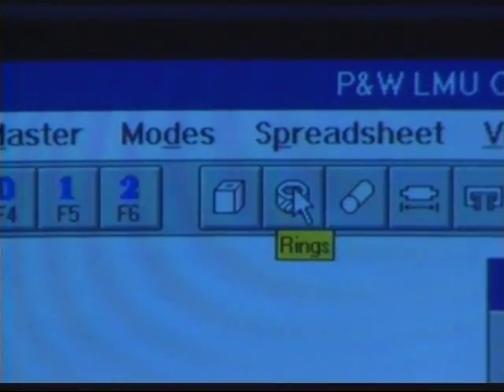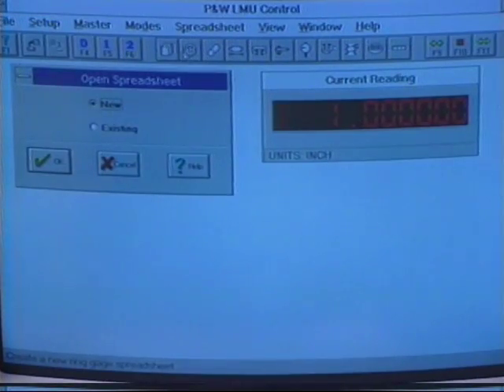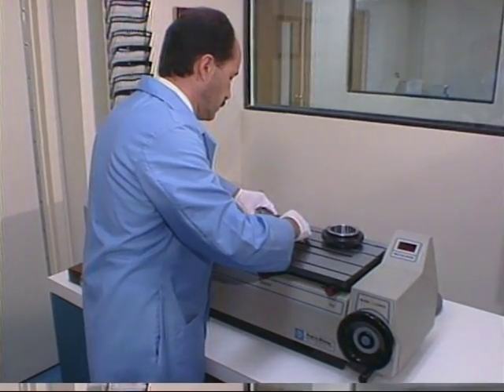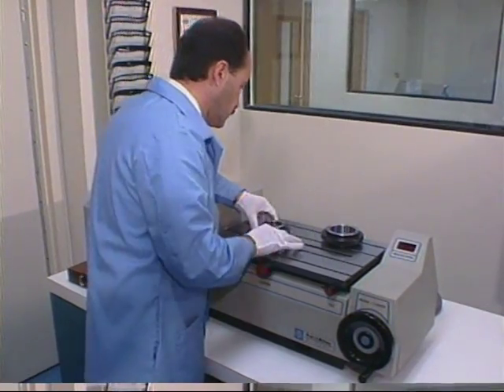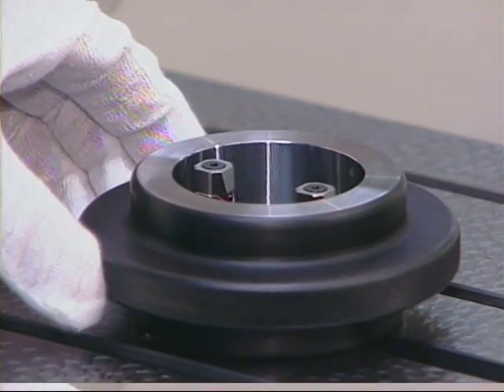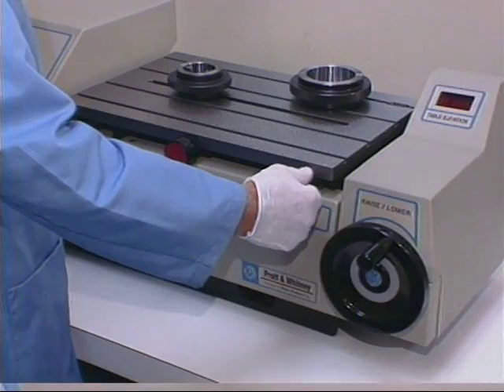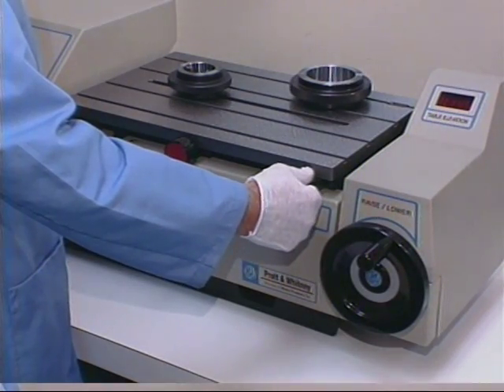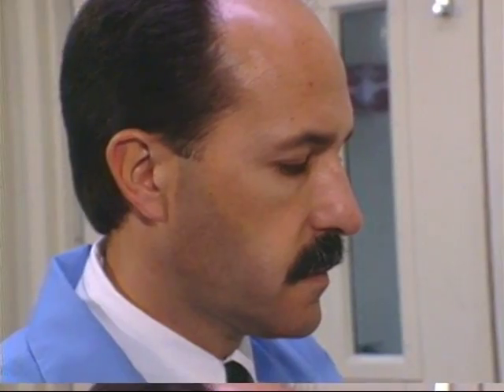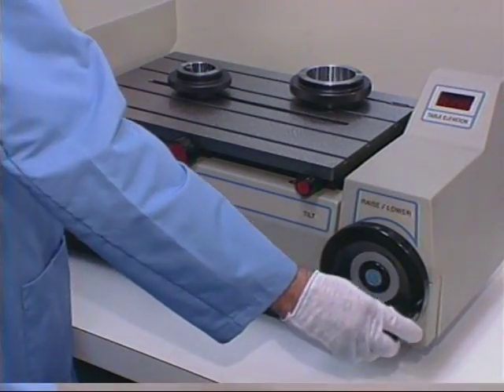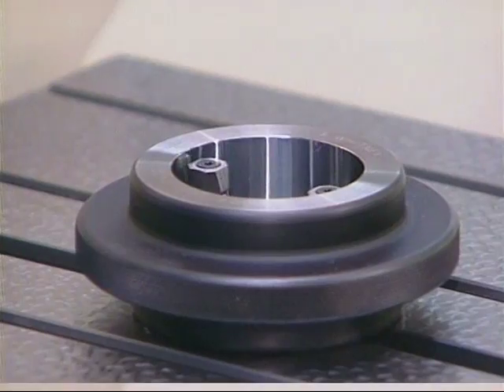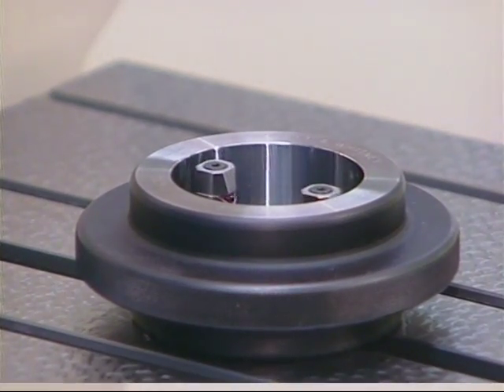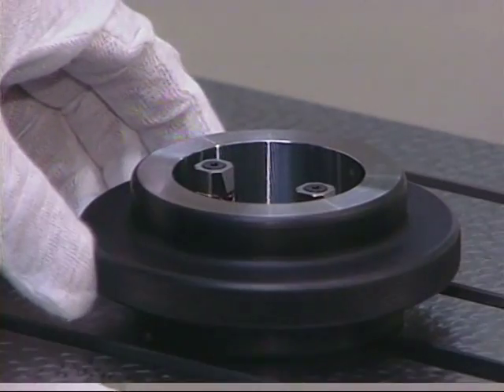To calibrate a ring gauge, select the ring gauge icon in MasterCal. Place the ring over the two probes and against the integrated locating posts to centralize the ring. The ring is quickly positioned by adjusting the table, first the tilt, then the center, while looking for a maximum reading. Once positioned, you can move the table up and down to measure the bottom, middle, and top of the ring. Rotate the ring 90 degrees and take 3 more readings.